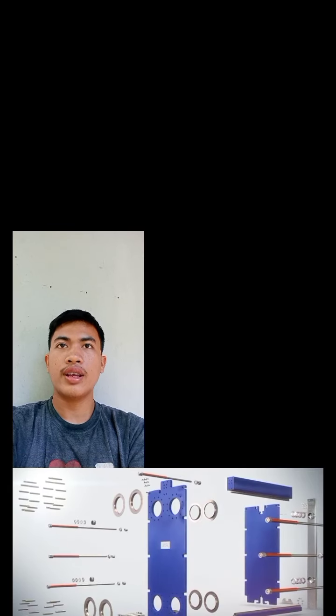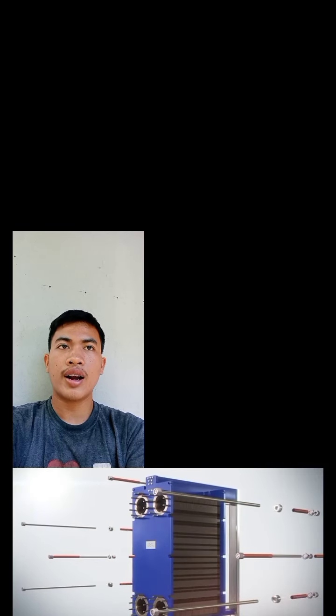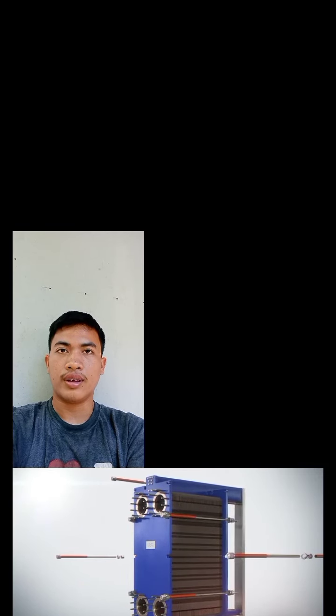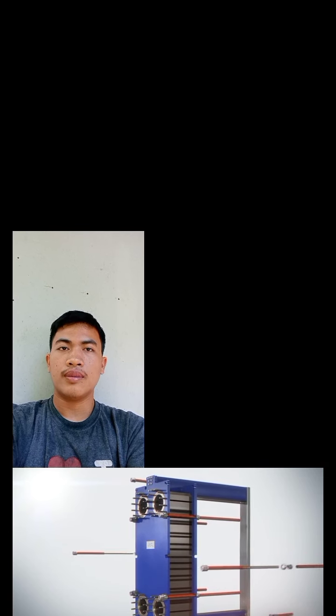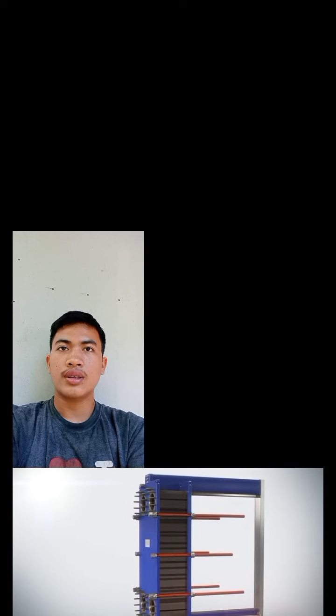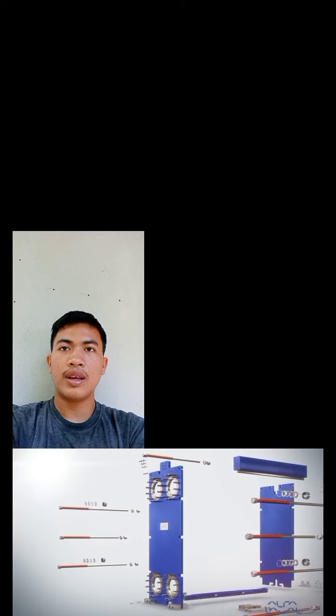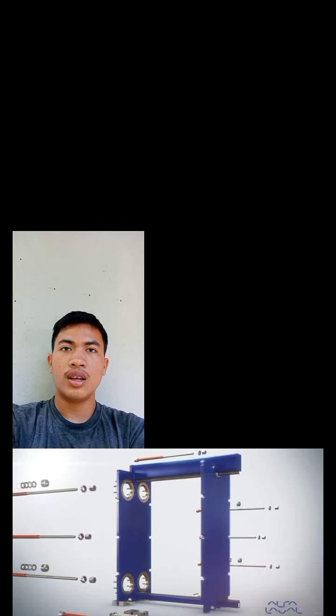Step 1. Loosen and remove bolts. Start the disassembly by loosening and removing all the bolts except for the circled ones above. Then loosen the circled bolts in increments of about half an inch until they are loosened enough to be removed safely. Make sure to loosen them in the indicated order to avoid stressing any of the components. If you are using a clean-in-place or CIP process, or simply inspecting the plates for fouling, then you can easily access the plates without removing them.